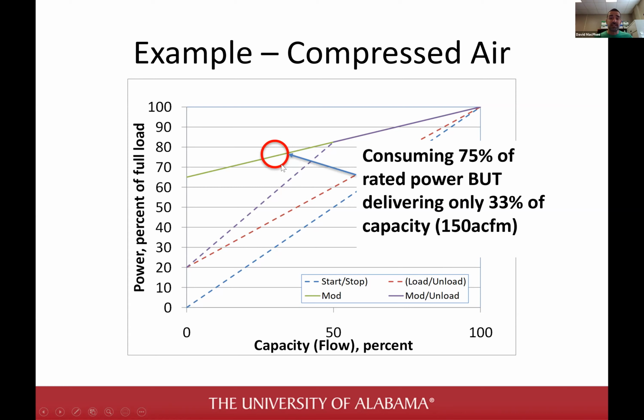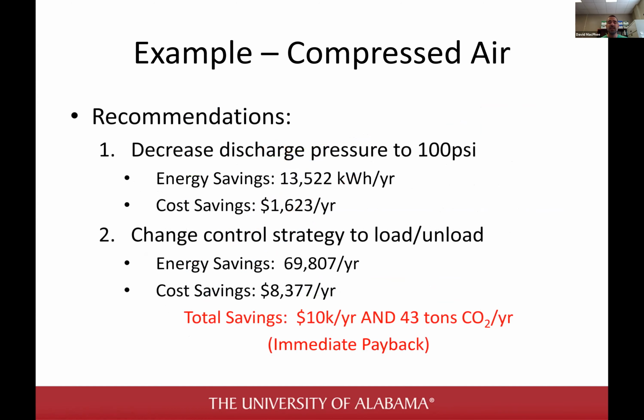It's fine to have an oversized compressor as long as the control strategy is such that you don't waste a lot of energy. This modulating butterfly valve is really very closed, and a lot of the energy going into making that compressed air is fighting against that inlet control valve. So this is an example of what I would say to this facility.